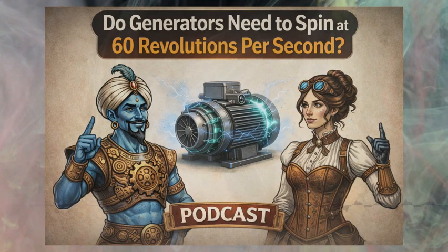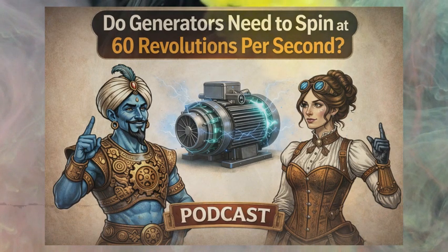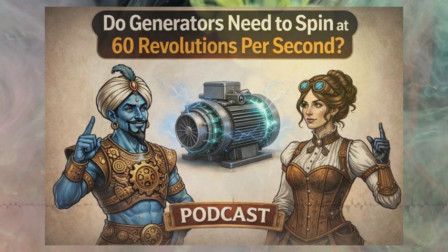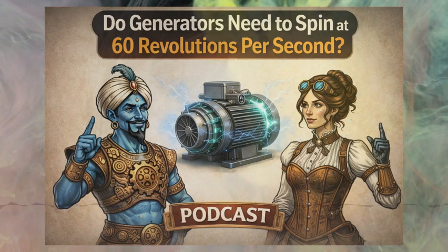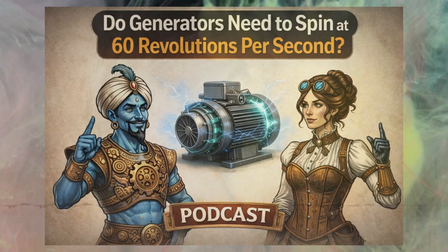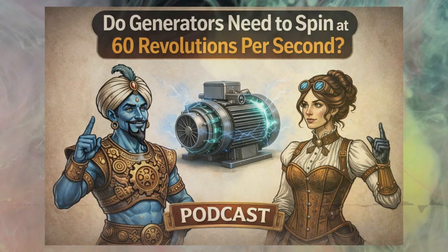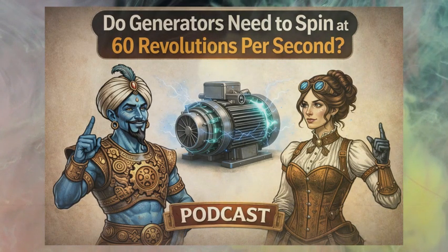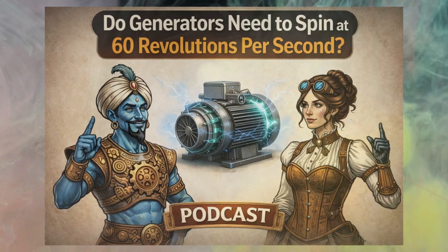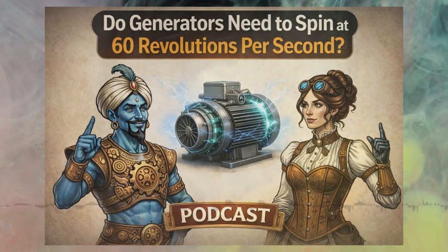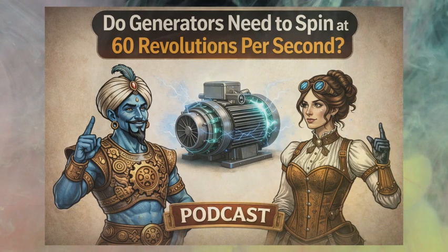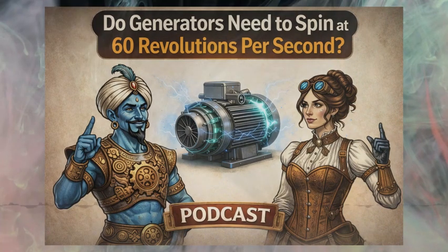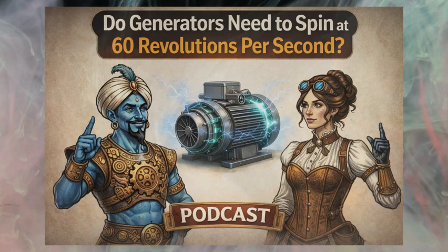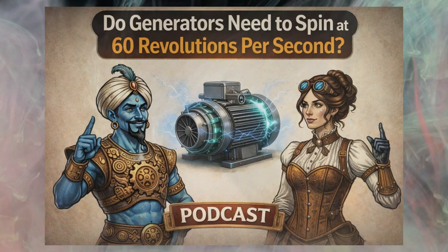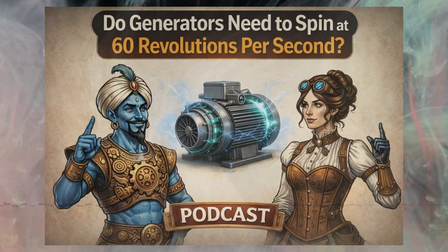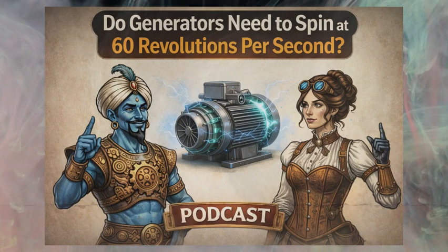It's all about stability and control. The sources point out that these exciters are often shunt-wound and self-excited, which is a fancy way of saying they are designed to produce a very stable DC voltage that doesn't fluctuate much as the main generator speeds up or slows down slightly. So it's a regulated power supply. A meticulously regulated power supply, because the strength of that DC current directly controls the final output voltage of the main alternator. There's usually an automatic voltage regulator, an AVR, that's constantly monitoring the grid voltage.